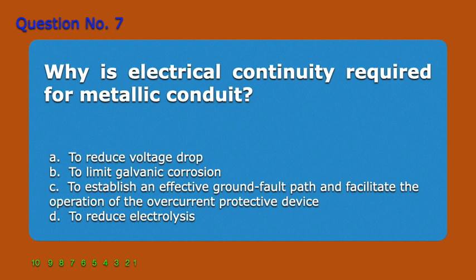Question number 7. Why is electrical continuity required for metallic conduit? A. To reduce voltage drop. B. To limit galvanic corrosion. C. To establish an effective ground fault path and facilitate the operation of the overcurrent protective device. D. To reduce electrolysis.